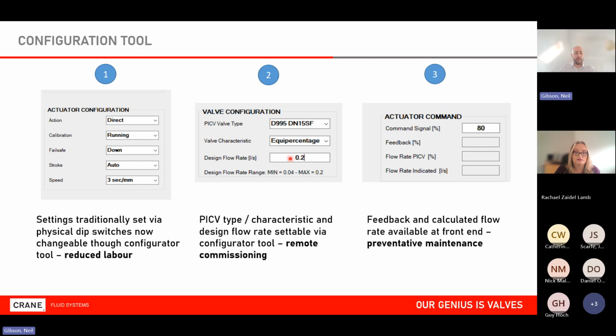And to set the flow rate, it's no harder than just typing in the number here and hitting enter, and the valve instantly responds, and it sets its new flow rate in approximately 10 to 15 seconds. And I can do that en masse. I could set it up so that I can send all of these values to all of the actuators individually addressed, and setup can take minutes rather than days and weeks. I can also get some feedback information via the actuator as well.